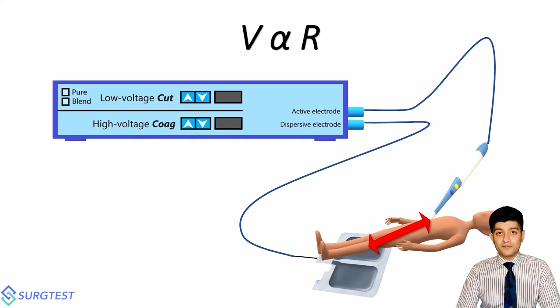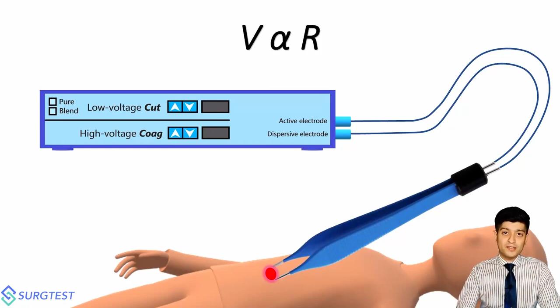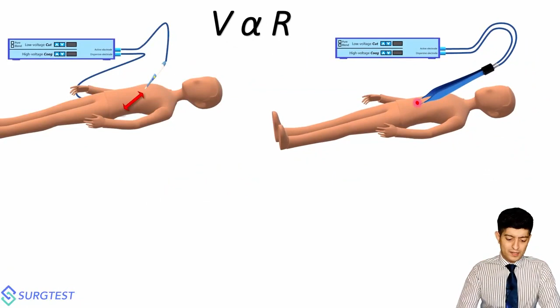So now see what's happening. When you use a monopolar energy device, you have so much of the patient tissues between the two electrodes. Because of the high amount of tissue, the resistance is also going to be high. In comparison, when you're using bipolar energy, for the same power delivery, the amount of tissue that has to be grasped within the two electrodes is small, so it's a lower resistance. Eventually, monopolar energy has more tissue between electrodes, higher resistance, therefore higher voltages are required. In stark contrast, for bipolar devices, there's a lower resistance, so a lower voltage for the same amount of power delivery. And this is the reason why bipolar devices are inherently safer than monopolar devices.